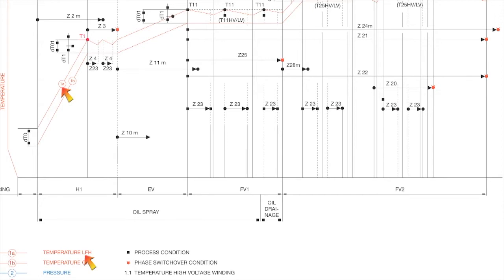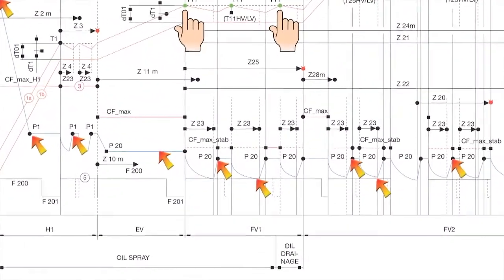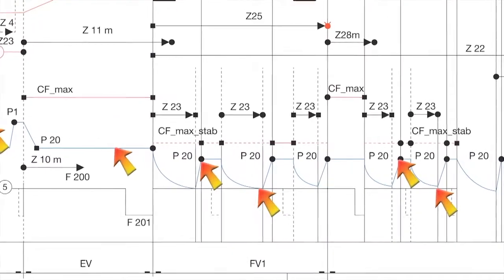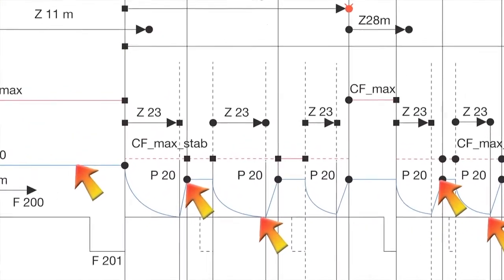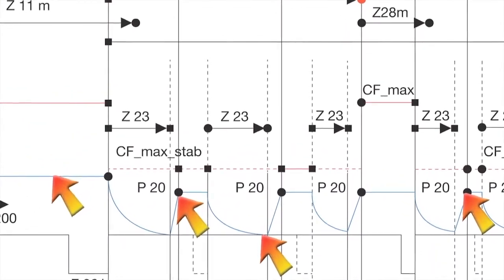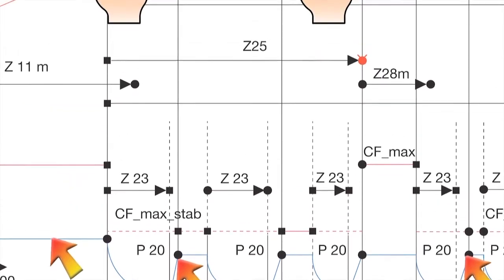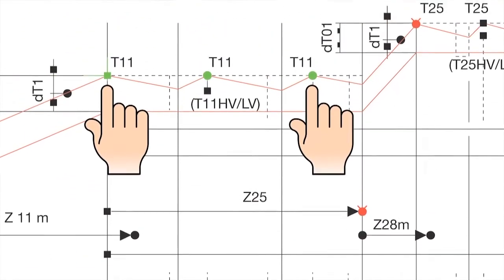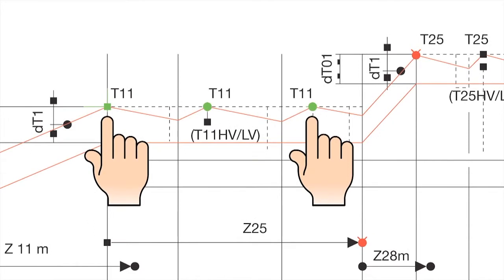Flashover is prevented through partially raising the pressure in the transformer tank with air between each evacuation. After reaching the time Z3, the process will go on with the next phase. Overview. Evacuation. The transformer is heated to the next temperature set point. Through vacuum stabilization, a flashover, according to the Paschen law, is prevented. Should for some reason the vacuum fall below P20, the LFH heating stops immediately.